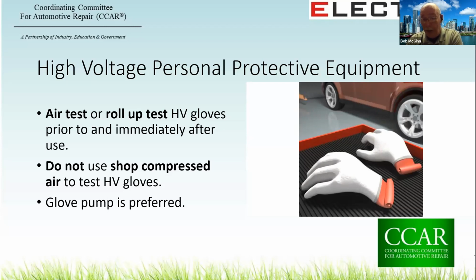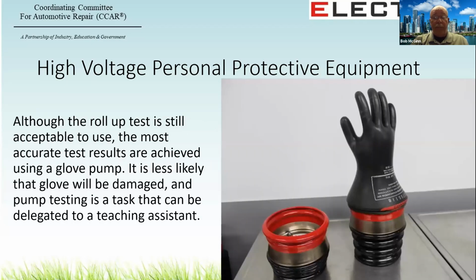Gloves can be pinholed by overinflation, and a pinhole is sufficient to convey a lethal shock. Not to mention that gloves are expensive. Our example was $130 US when we purchased them, and they were expired when they arrived. If you're teaching high voltage at full scale, then a glove pump is a must. The task of testing is something you can delegate to a competent student or a subordinate teaching assistant to make sure that the gloves that you're using in shop are in top condition and to be able to remove those gloves that fail.